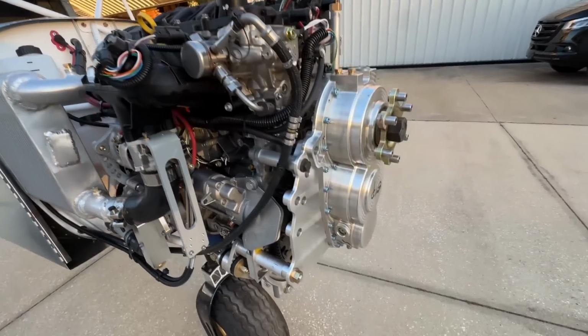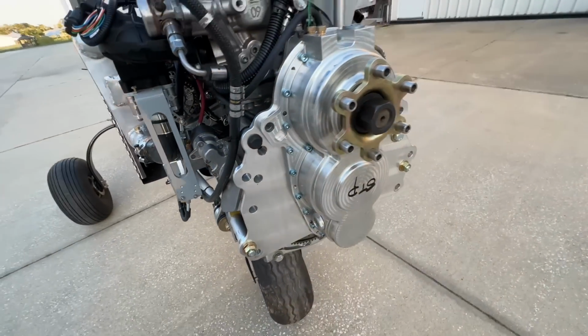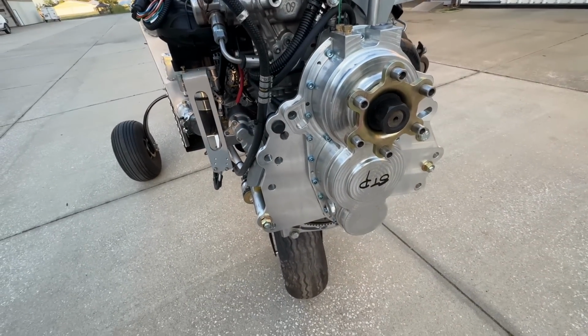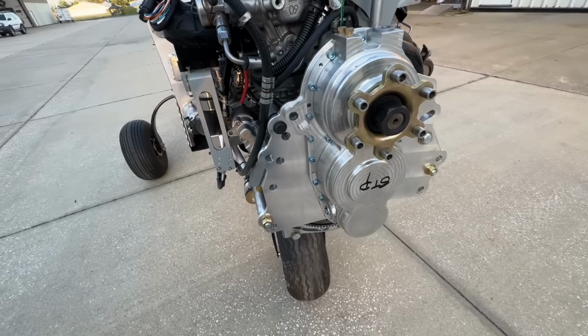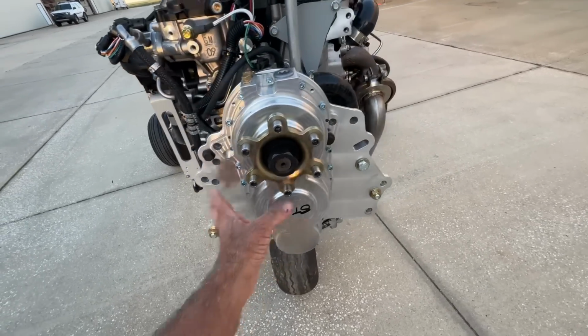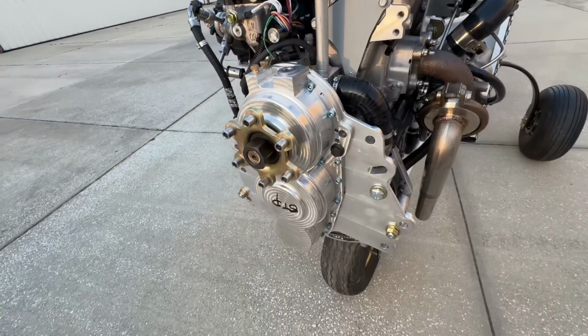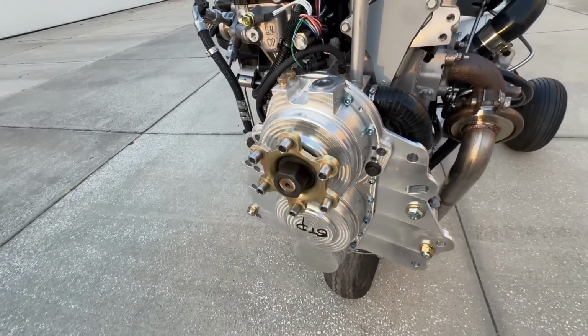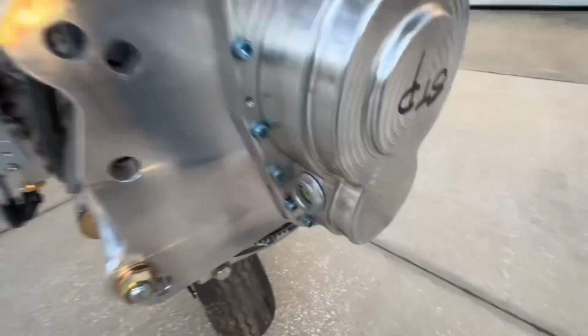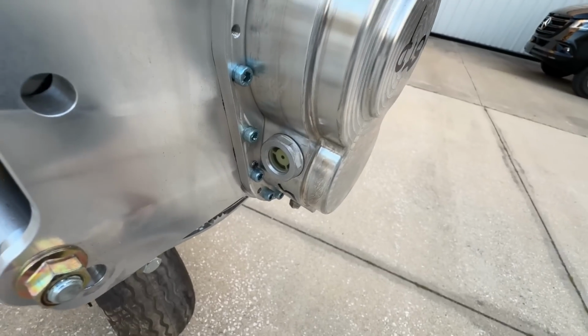Then for the gearbox, use 9 to 10 ounces, no more than 10. More is not better, it's just more heat in the gearbox. We aim for 10, but no more than 10. The sight glass will read full and more than full when you have 10 ounces in there.